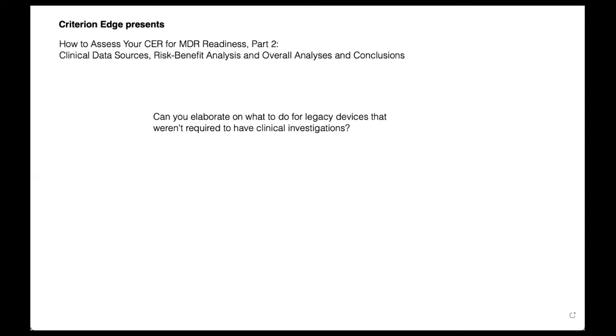And it's not really a problem. It's just an approach. You take a different approach in the CER, where it becomes very important for you to establish safety and performance objectives for your competitor device, so that you can use those to measure your own device's clinical data, what you do have on your legacy device, back to those robust safety and performance outcomes and acceptance criteria.